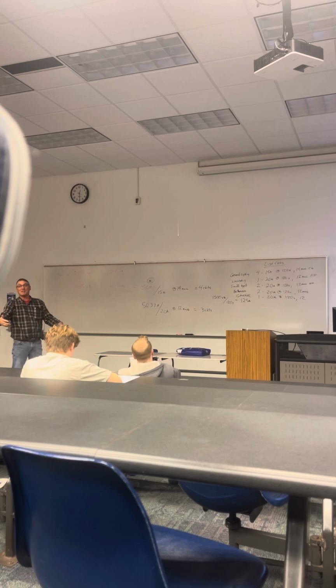So like basements, if it's a full basement underneath, you have to provide a circuit. I didn't tell you we had a full basement. But you have to provide a circuit for it, but it doesn't come into the calculation for general lighting load. So general lighting is just for livable spaces. Absolutely. Oh, right. Okay.